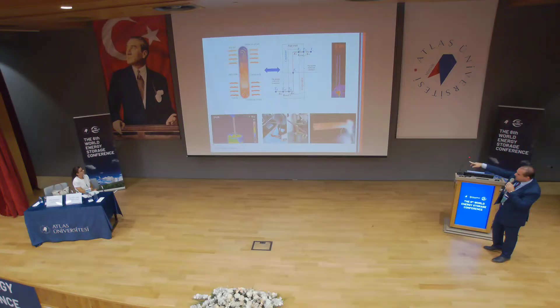Digging further: if we take several of those heat pipes and put many together in a box, separated by a plate, allowing a hot fluid to run through the lower chamber and a colder fluid through the upper chamber, these heat pipes act as sinks. They absorb heat from the bottom and shift it to the top, transferring heat to the fluid passively. In a conventional system, you can only do that with a flow running through, but because these are heat pipes, it's done passively. The only movement is the hot and cold streams moving through the two chambers to allow the heat transfer.